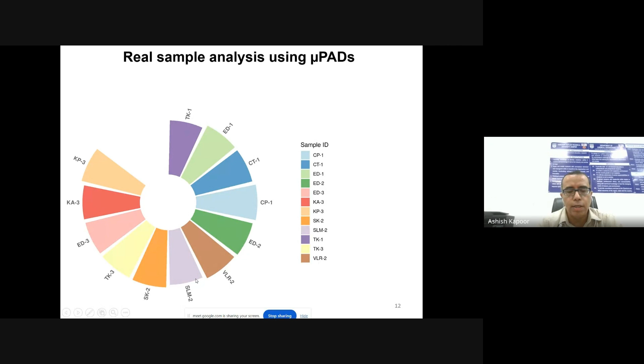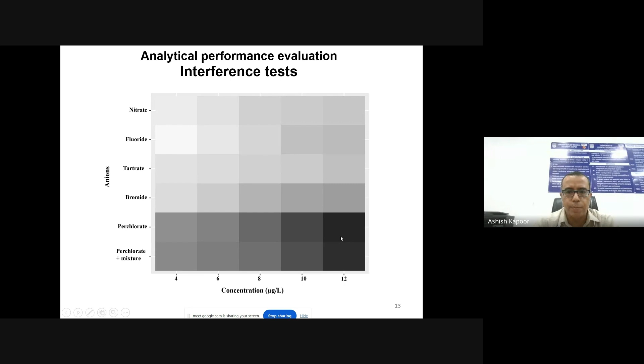Now, to validate such a sensor, it is also required to perform various other tests, including the interference test. So we tested several other ions which can be present along with it in the water, to see whether they will interfere with the testing of the perchlorate or not. All these individual ions were tested, and then they were also mixed with perchlorate solution of known concentration and tested. The results were quite promising: the device was not susceptible to interference from the other parameters.